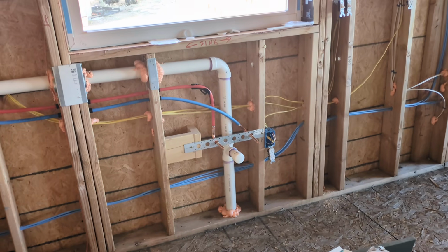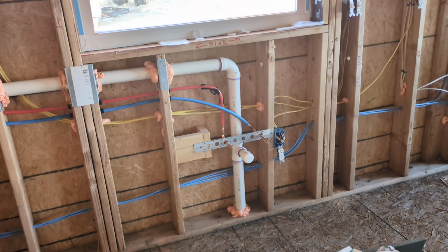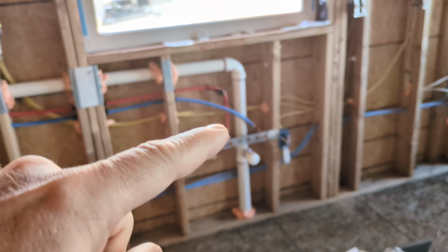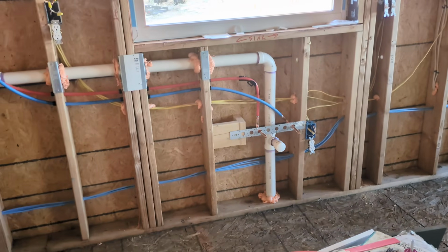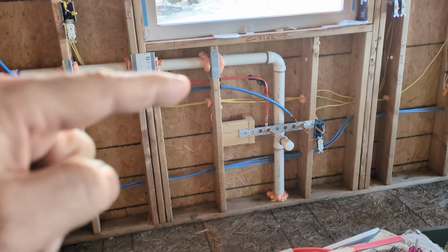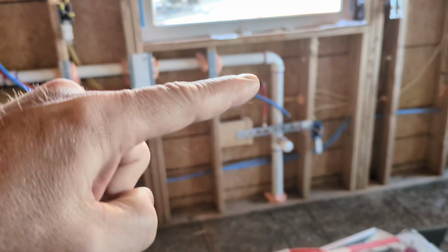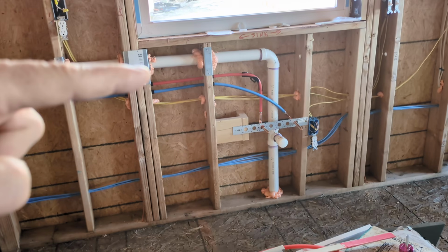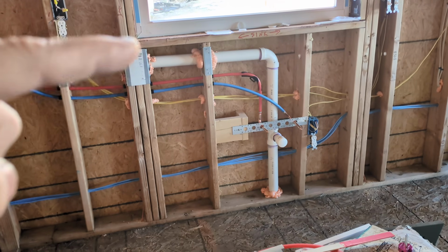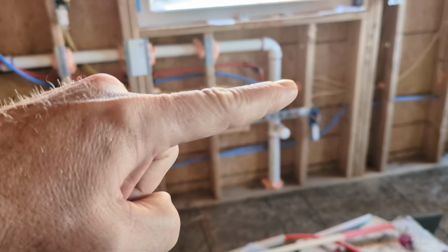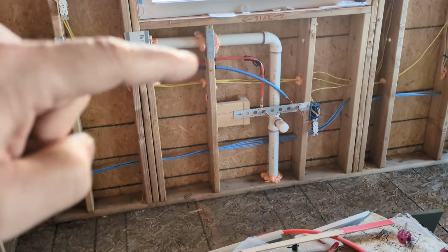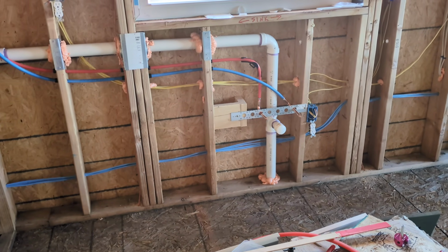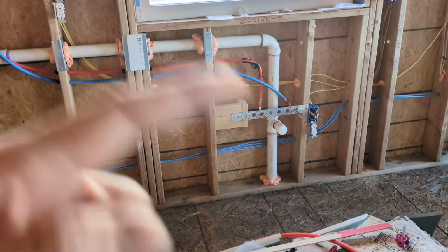And when that water goes down, it's going to draw a huge vacuum in the pipe. If that vent is below the level of it, it has the potential of sucking water out of other traps, through a siphon effect. So what they want is for the vent here, sorry for the focus, to be above the flood level of the sink. And the problem is that with a kitchen sink, the flood level is going to be up to about here. So with an air admittance valve, you can get it right up to the vanity. And what we're really trying to do here is provide for that.